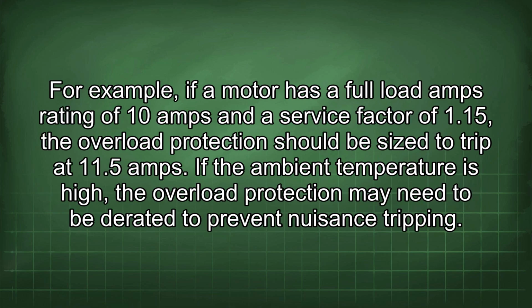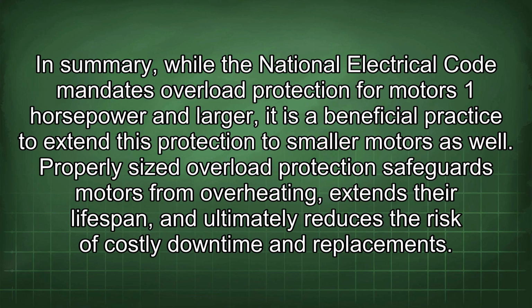For example, if a motor has a full load amps rating of 10 amps and a service factor of 1.15, the overload protection should be sized to trip at 11.5 amps. If the ambient temperature is high, the overload protection may need to be derated to prevent nuisance tripping. In summary, while the National Electrical Code mandates overload protection for motors 1 horsepower and larger, it is a beneficial practice to extend this protection to smaller motors as well.